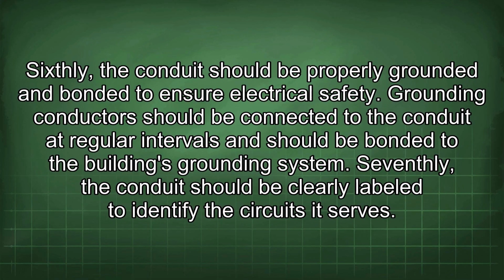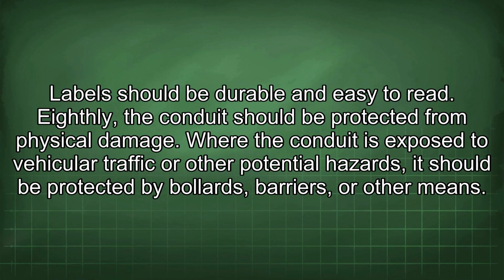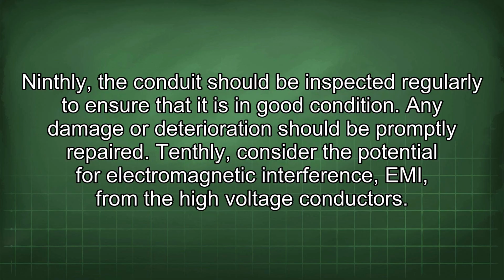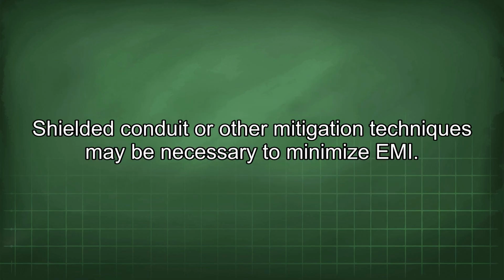Seventhly, the conduit should be clearly labeled to identify the circuits it serves. Labels should be durable and easy to read. Eighthly, the conduit should be protected from physical damage. Where the conduit is exposed to vehicular traffic or other potential hazards, it should be protected by bollards, barriers, or other means. Ninthly, the conduit should be inspected regularly to ensure that it is in good condition. Any damage or deterioration should be promptly repaired. Tenthly, consider the potential for electromagnetic interference, EMI, from the high voltage conductors. Shielded conduit or other mitigation techniques may be necessary to minimize EMI.